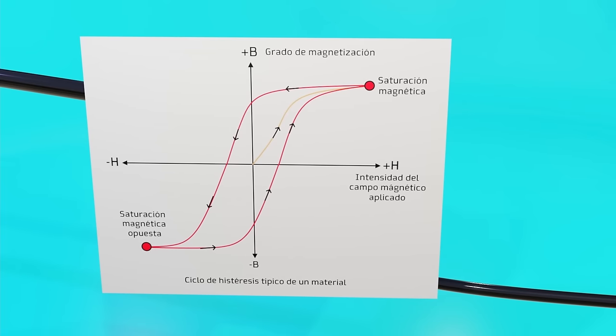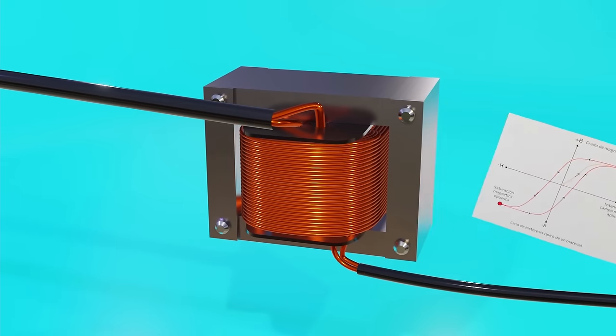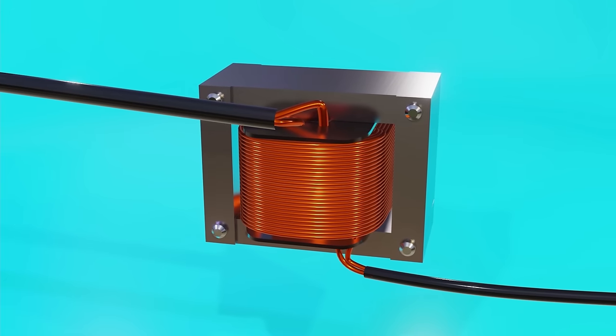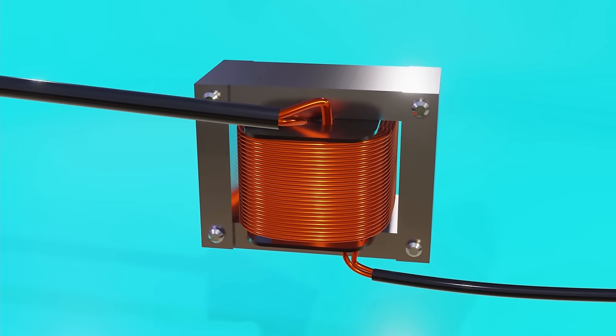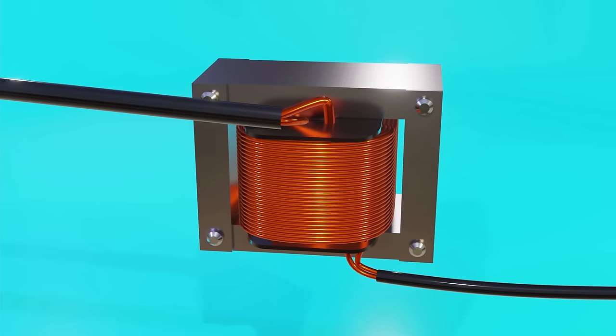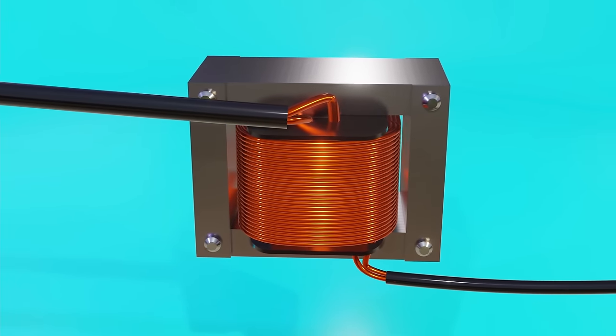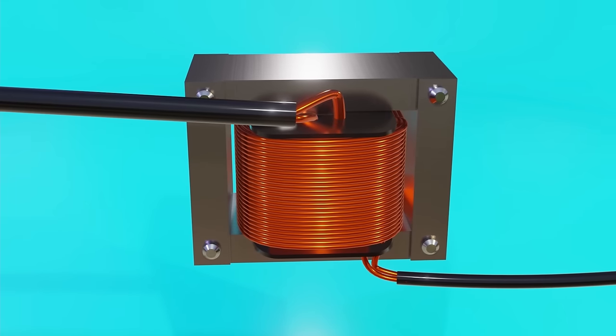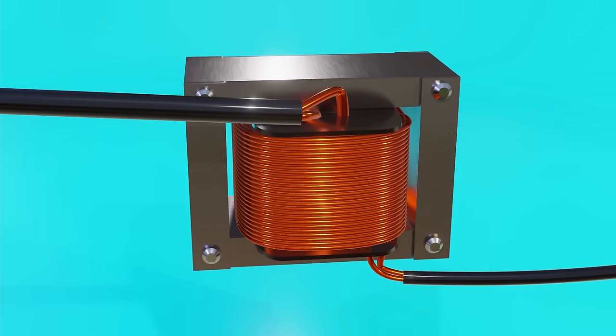Luckily, the steel and silicon cores also have hysteresis losses much smaller than a common steel core, which is why they are ideal for a large number of applications, in addition to being relatively cheap to produce. However, they have a high density, which causes an increase in the weight of the transformers. Also when working with frequencies that exceed hundreds of thousands of hertz, eddy current losses and the temperature generated as a result of their dissipation exceed acceptable limits.